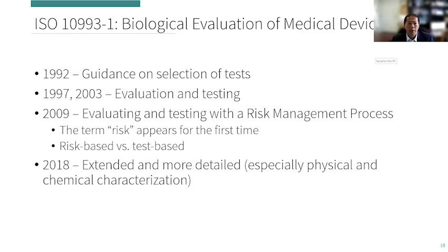which was critical because that was when a risk-based approach was first described. So the term risk appears for the first time in the ISO standard, and rather than being focused on conducting tests, it became more focused on understanding the risks of the materials and the device to assess whether additional evaluations needed to be conducted.